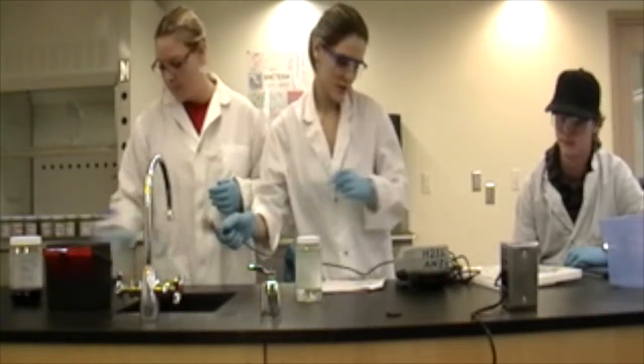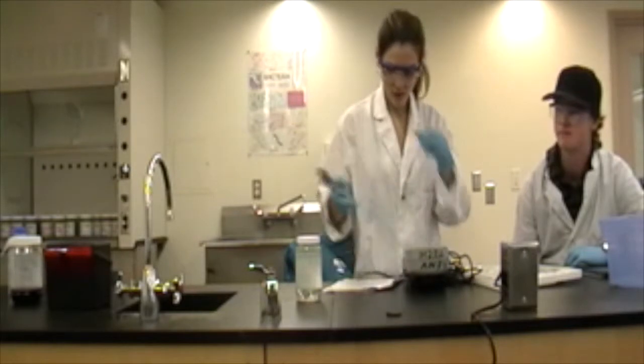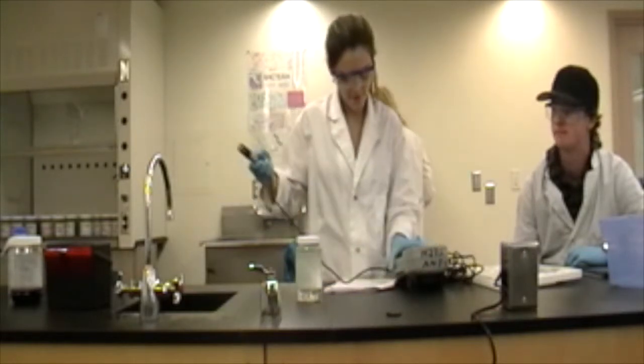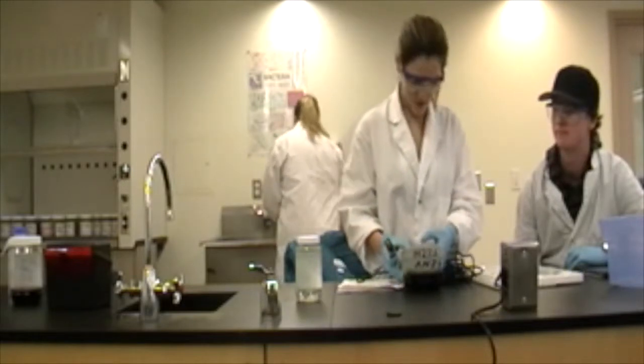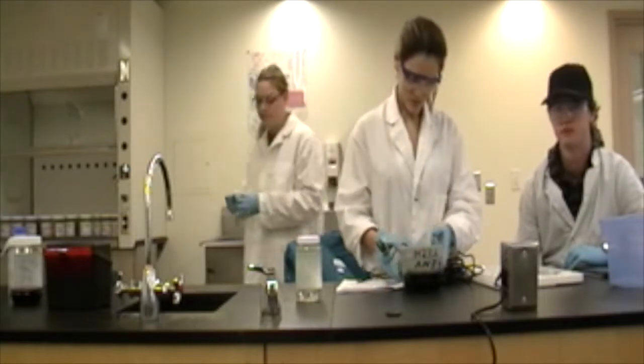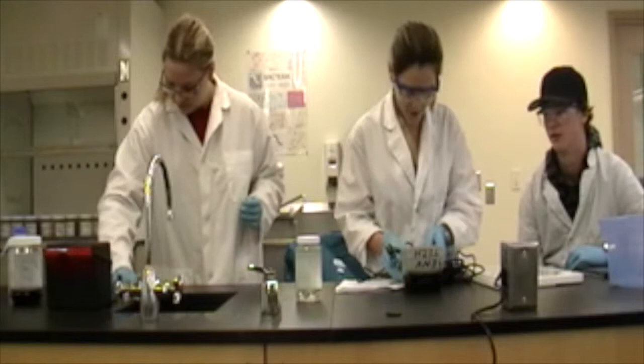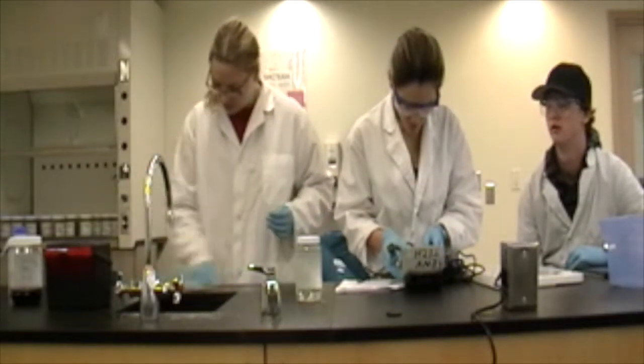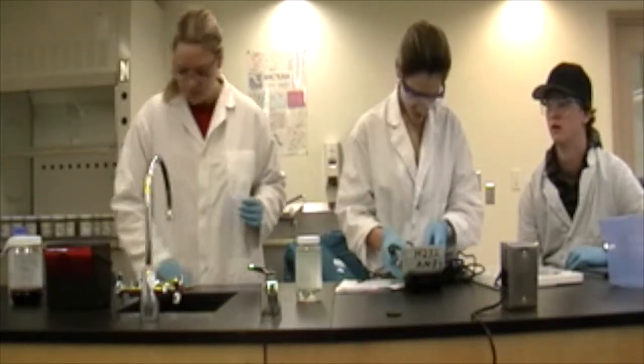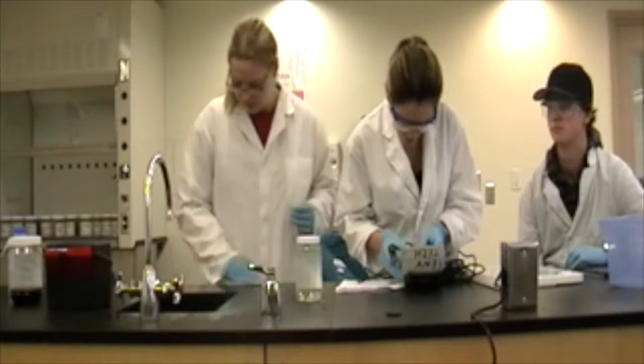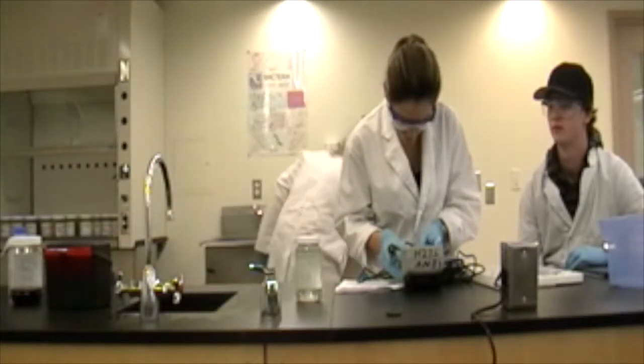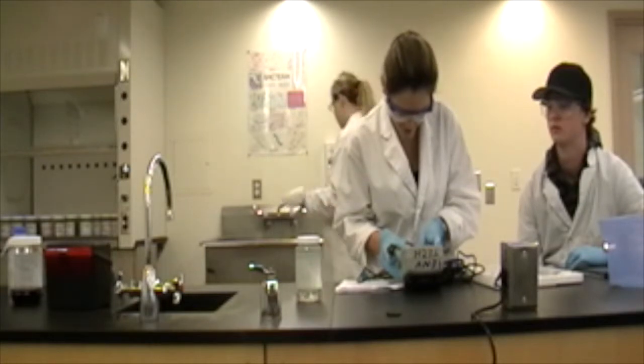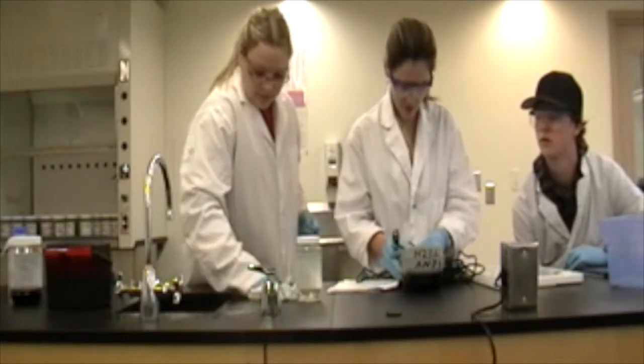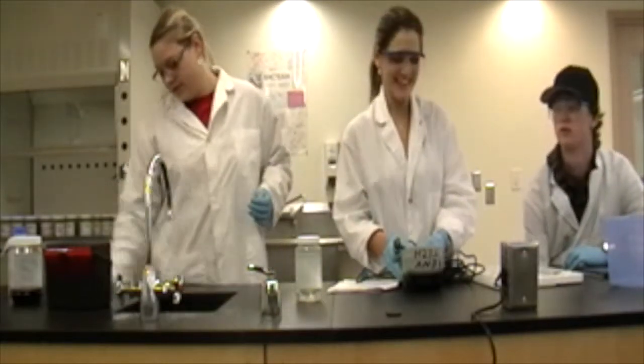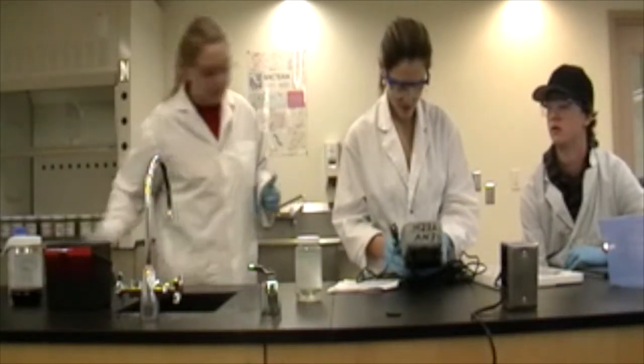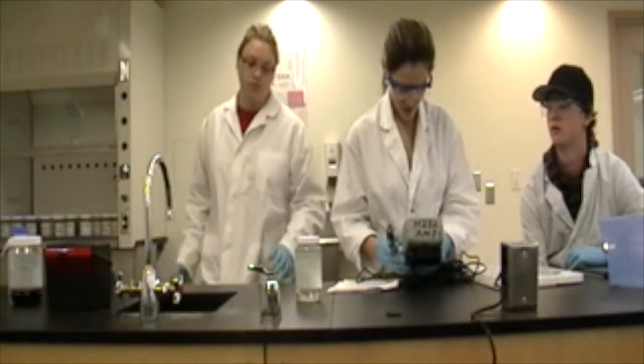Alrighty. That's when you're going to want to turn your instrument on. Okay. So to calibrate, you're going to press and hold both the up and down arrow at the same time, and click enter, which is an arrow. And you're going to want to go to milligrams per liter. Oh, shoot. And we're going to calibrate for our number, which was 8.6.